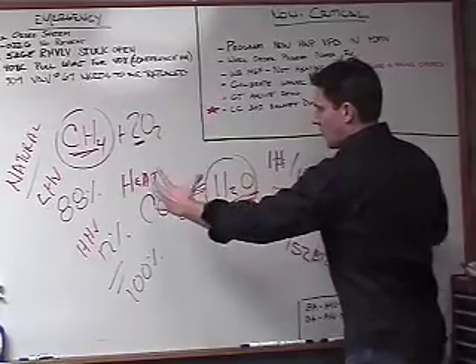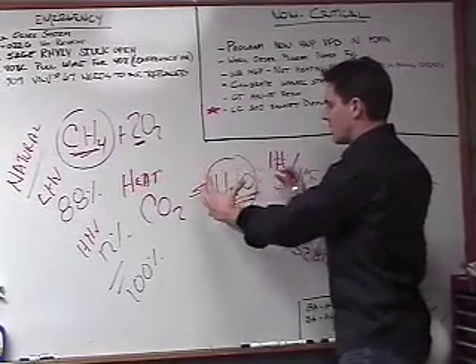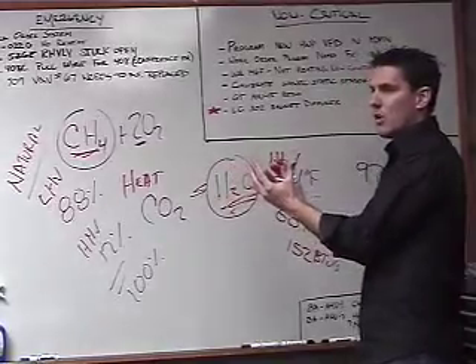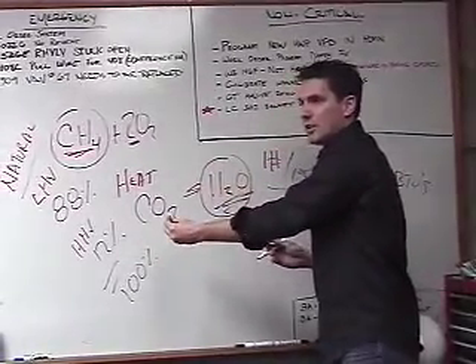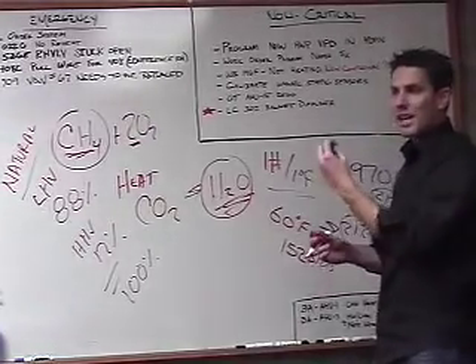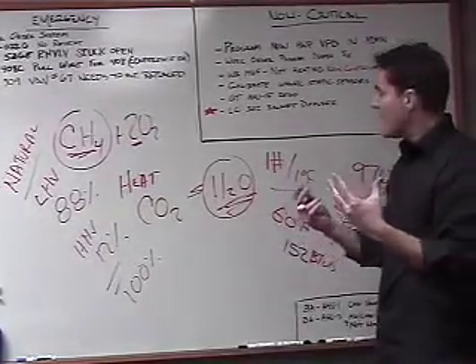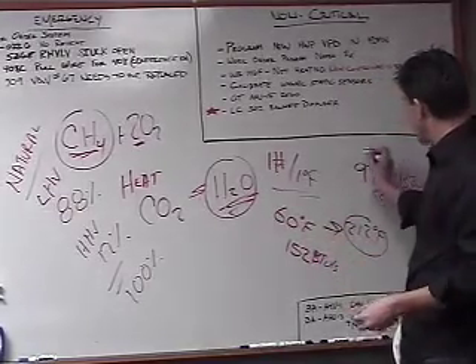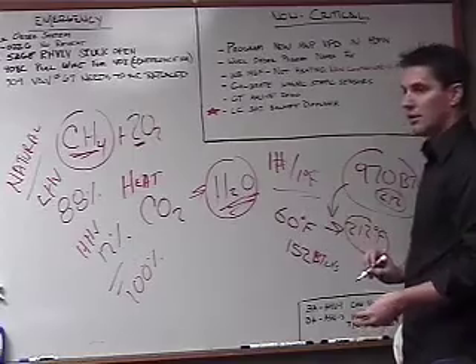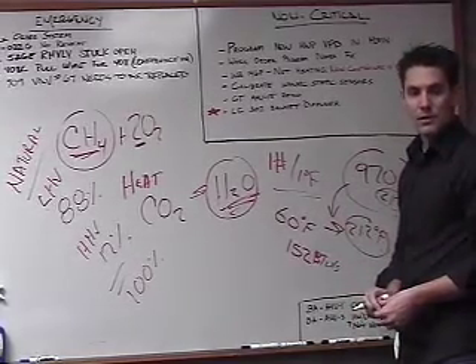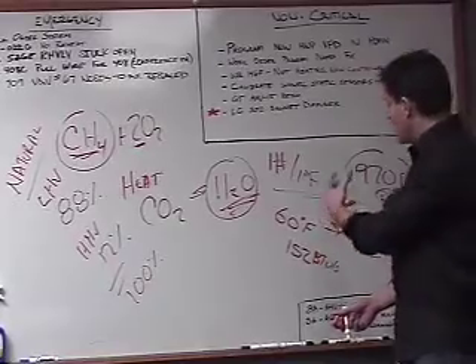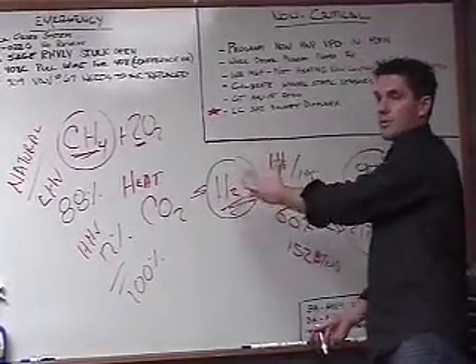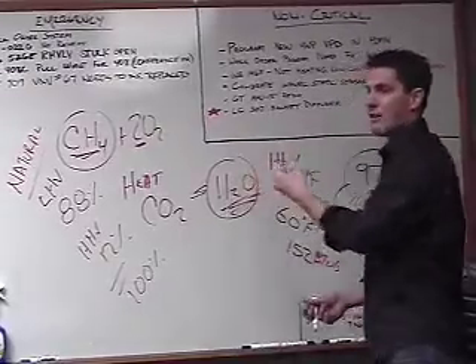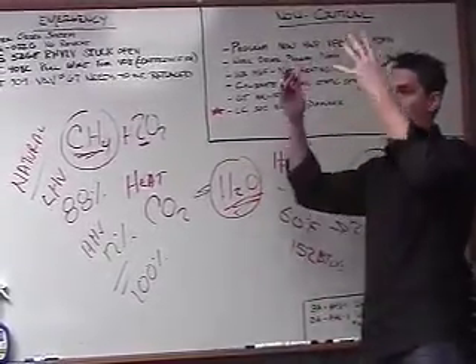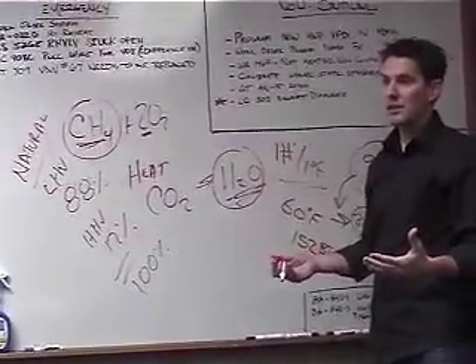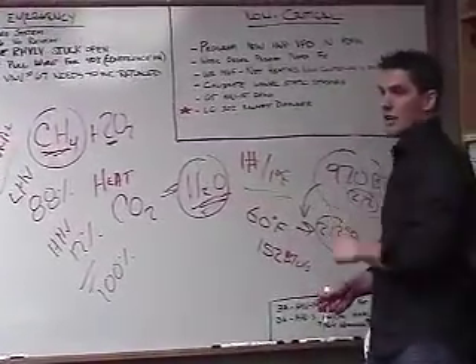So with this chemical reaction that's occurring during the process of combustion, I'm creating H2O. This H2O absorbs my heat energy, this 970 BTUs, to turn into a gas. If I take this pound of steam and turn it back into a liquid, I'm going to give up 970 BTUs. So I'm giving up heat energy. If I don't take that energy out of this water vapor, and all that steam goes up my stack with all my hot flue products, I'm not condensing. I've just wasted a measurable amount of energy.